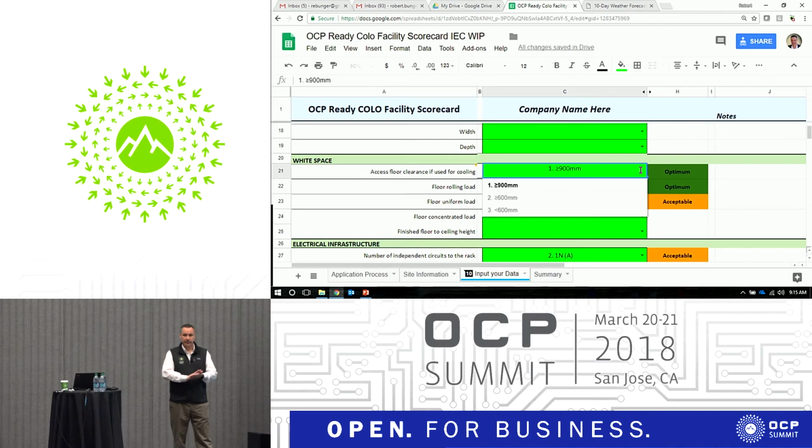Now, for those that aren't familiar, I think the initial Facebook Open Compute rack was in the range of 8 kW. Does that sound about right? I think for those in the know, they can be up to maybe 10 to 12 right now. So they're not insanely high, but that's like average. It's super easy to get racks in the 20 kW range if you really stack them up. So it's possible to do that with Open Compute gear.